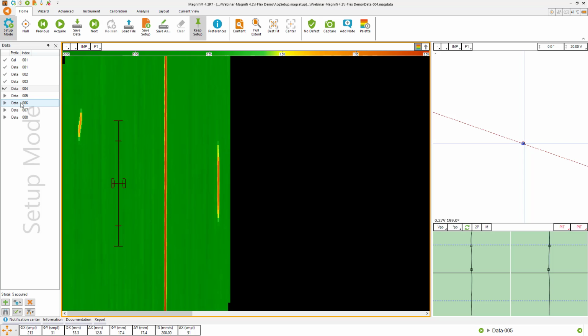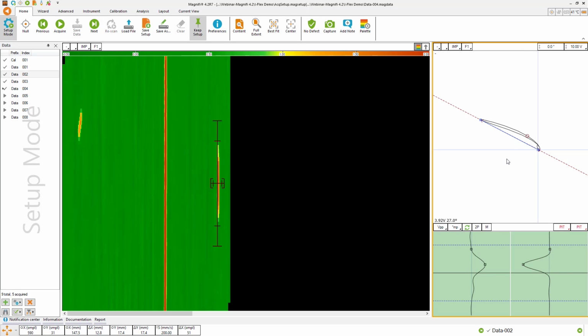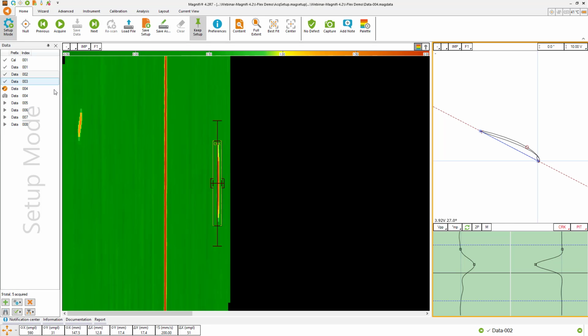The data file will get populated, and if a report is made, someone can come here, select a file, change the measurement mode, let's say an average peak measurement for the phase, and enter a report entry if any reporting has been defined and if a sizing curve has been defined. If there is no sizing curve, only the code will be added for that specific file.